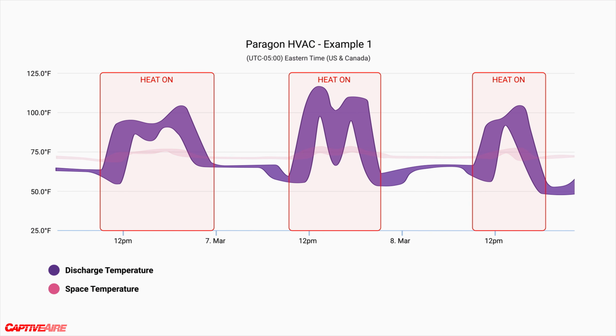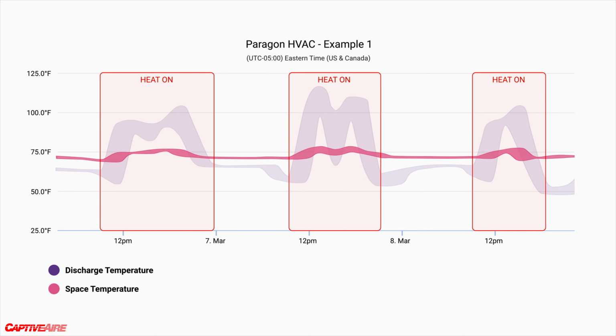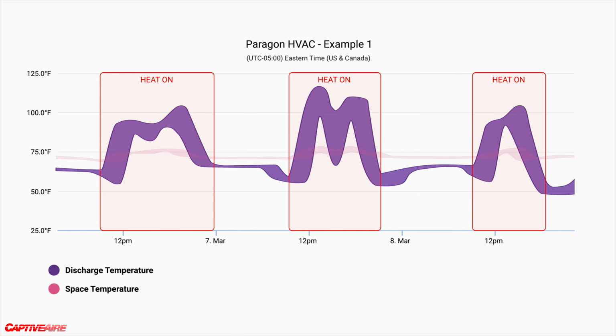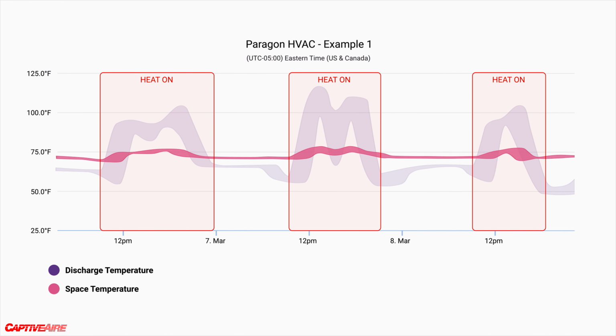Our system operates with a modulating heat. So as you turn on heat, if the space doesn't need that much heat, the discharge temps should be going down much lower. And what we're finding is the discharge temps were staying at like 100 degrees, even though the space didn't want heat at that point. So this was clearly an issue related with that modulating gas valve. We could see the software even wanted to pull that heat back, but it wasn't able to.